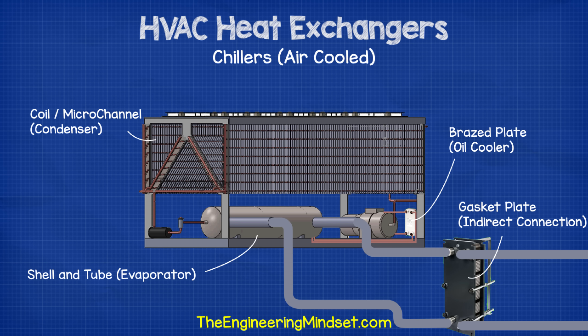A chiller will use either a shell and tube heat exchanger, a plate heat exchanger or a fin tube heat exchanger — and many chillers use a combination of all of these. For example, an air cooled chiller may use a shell and tube heat exchanger for the evaporator, a fin tube or micro channel heat exchanger for the condenser, a brazed plate heat exchanger for the compressor's oil lubrication cooling, and a gasket plate heat exchanger to indirectly connect the chiller to the central cooling circuit.